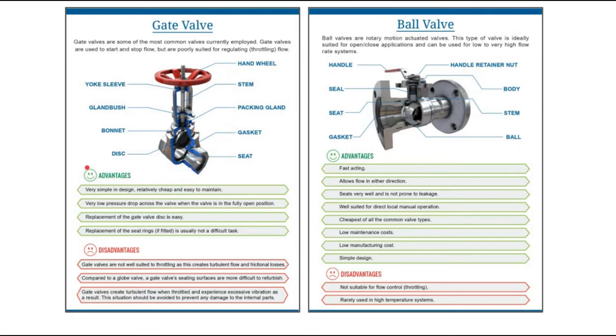The advantages of a gate valve: it is very simple in design, relatively cheap, and easy to maintain. There is very low pressure drop across the valve when it is in the fully open position. The replacement of the gate valve disc is easy, which is important because the disc can get damaged at times. So the gate valve is a good choice when you need to replace the disc easily.